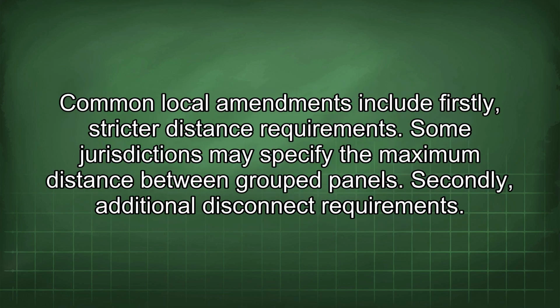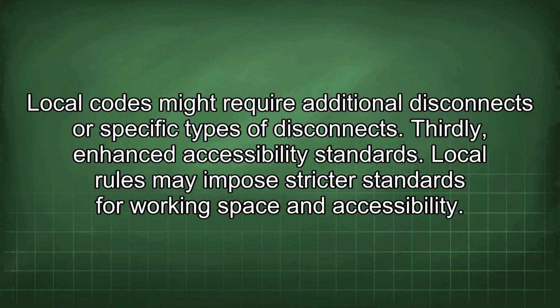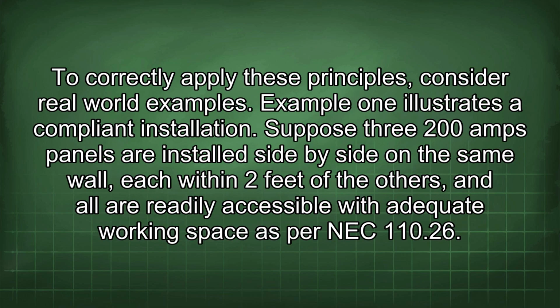Common local amendments include, firstly, stricter distance requirements. Some jurisdictions may specify the maximum distance between grouped panels. Secondly, additional disconnect requirements. Local codes might require additional disconnects or specific types of disconnects. Thirdly, enhanced accessibility standards. Local rules may impose stricter standards for working space and accessibility. To correctly apply these principles, consider real-world examples.